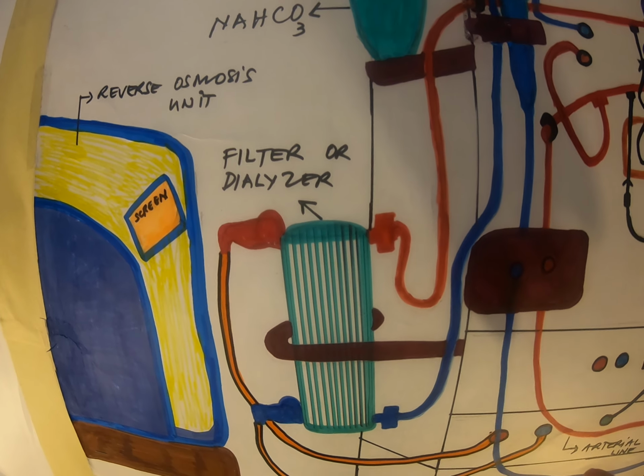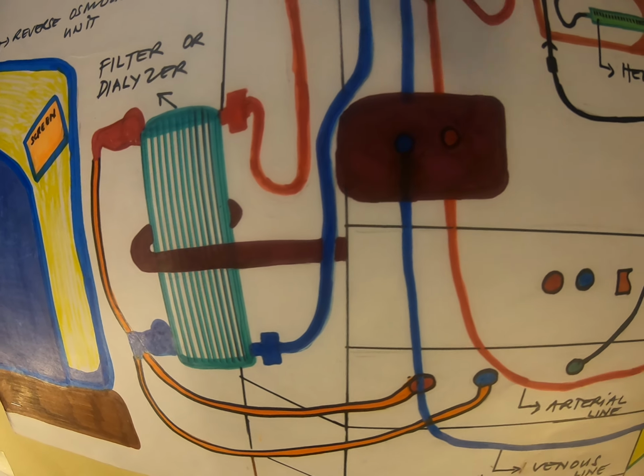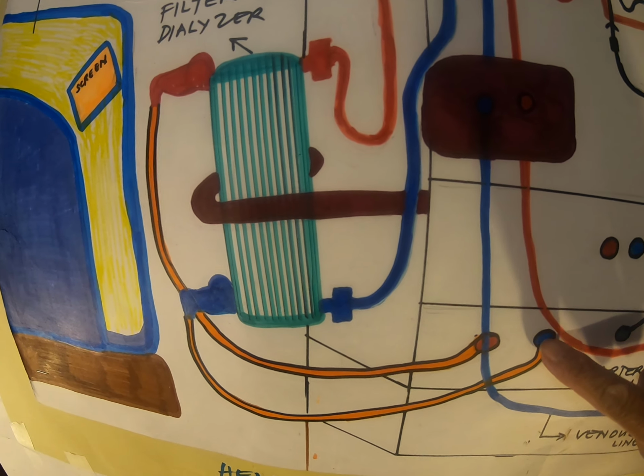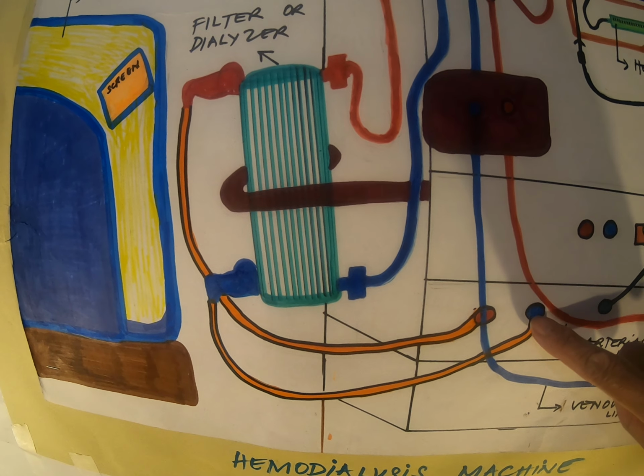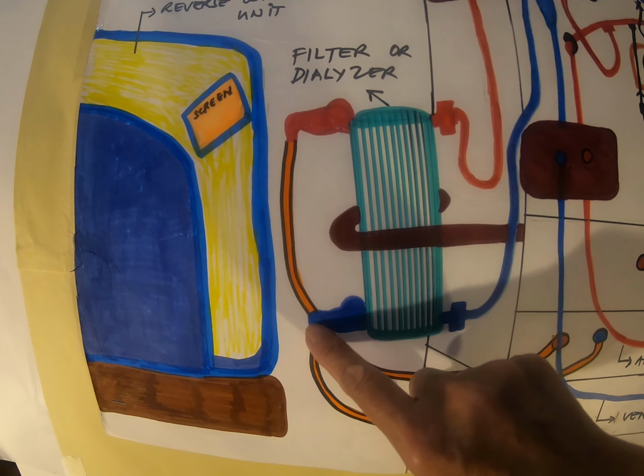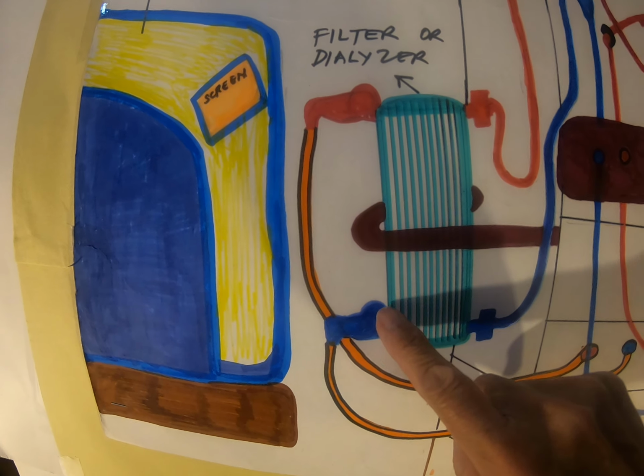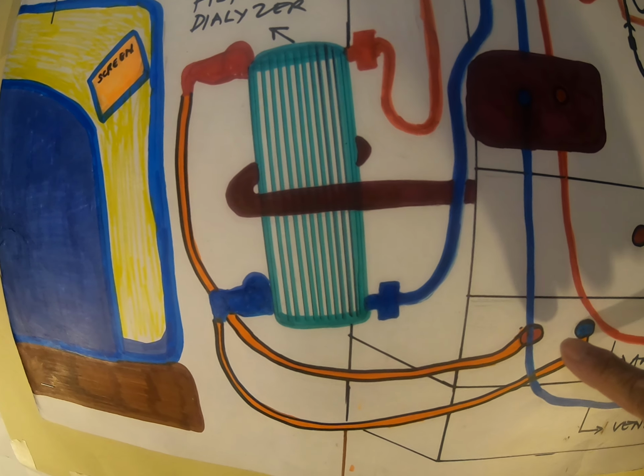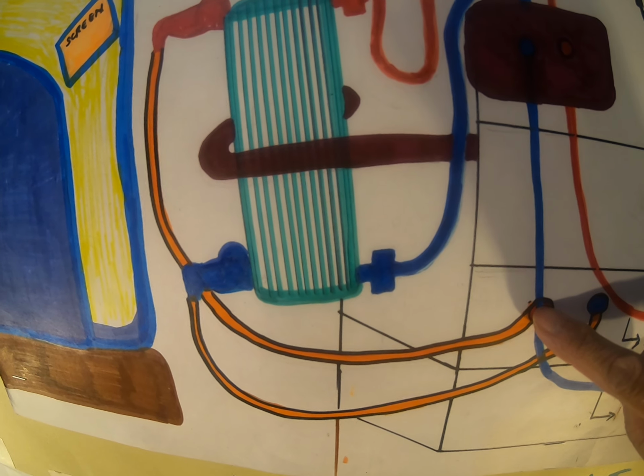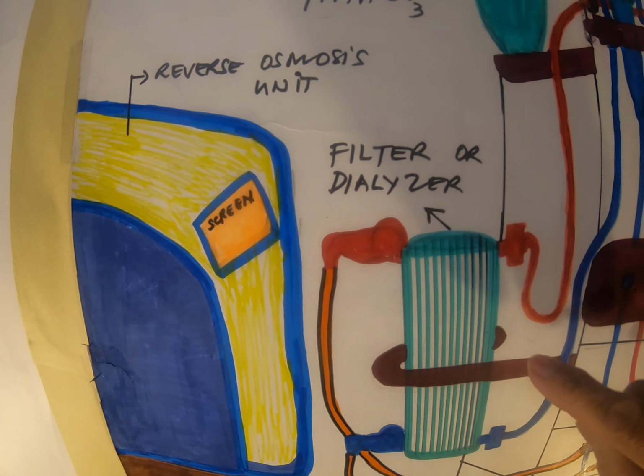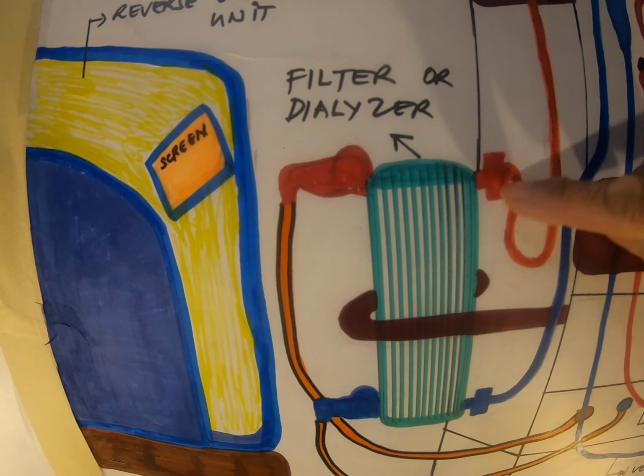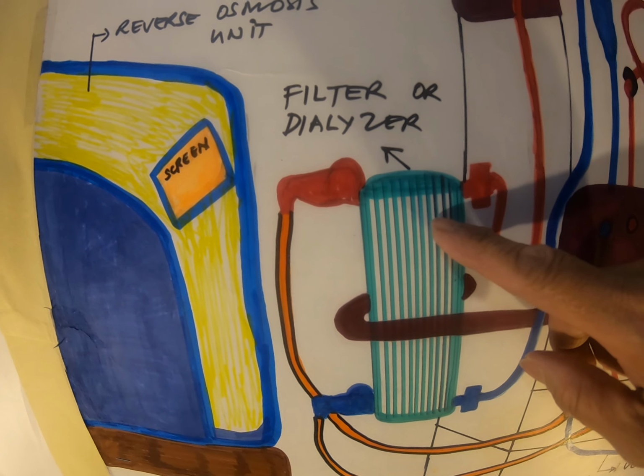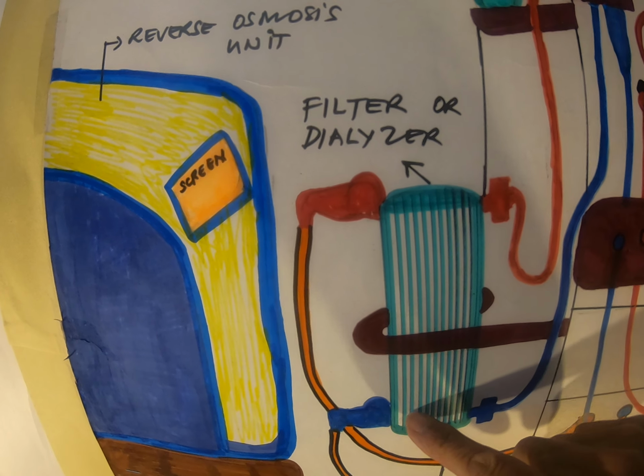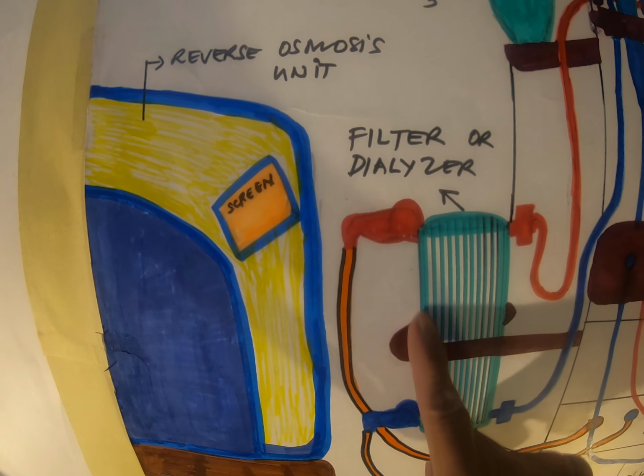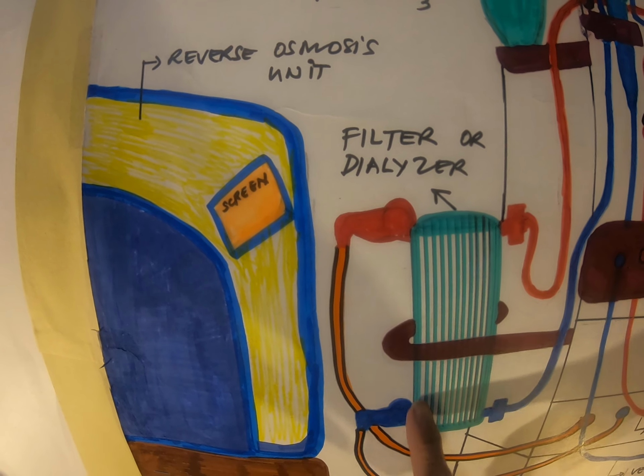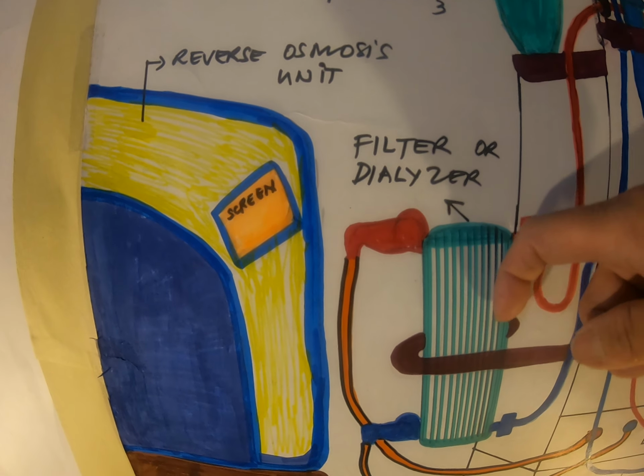So we have this fluid tube. These are the dialysis tubes. The dialysis tubes here, blue, go from the machine to the filter or to the dialyzer, going here at the bottom. This is where the connection is located. And we have also this arterial fluid tube that is connected to this part in here. So the blood goes down through the hollow fibers. We all know that there's diffusion and ultrafiltration. And then the dialysate goes up. That is the mode of mobility of this dialysis. It goes up as the blood goes down.